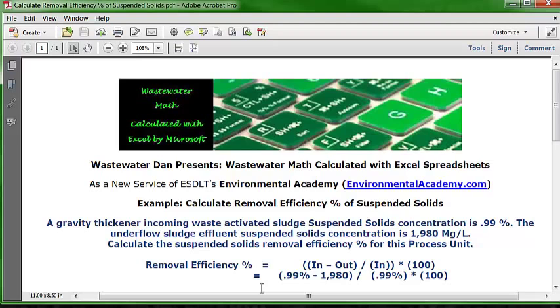Right under that I've put the numbers we have to work with. The number in is 0.99 percent — we're going to convert that to milligrams per liter or PPM — minus 1,980, which is the PPM or milligrams per liter of the effluent. We divide that net number by the incoming number, again expressed as parts per million, and multiply by 100.